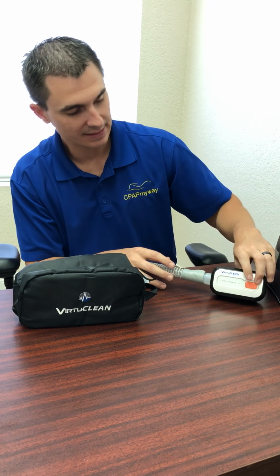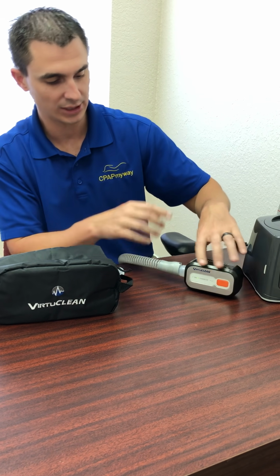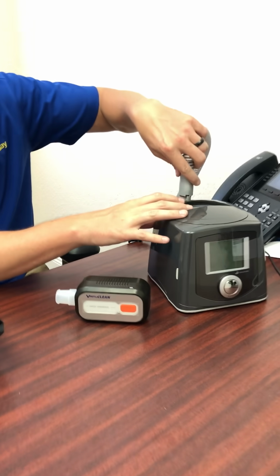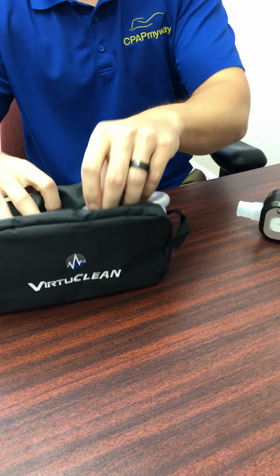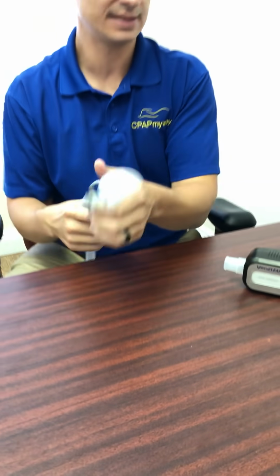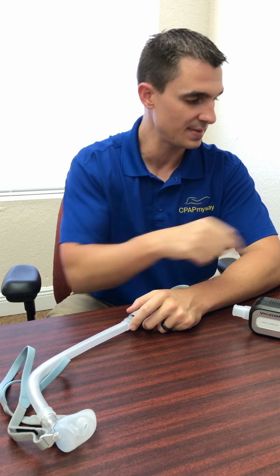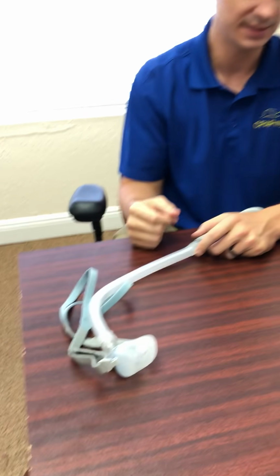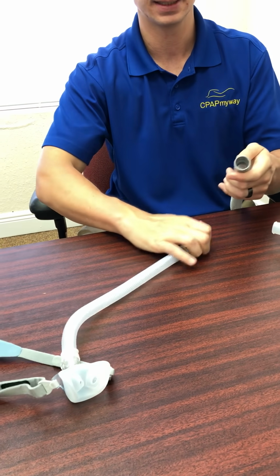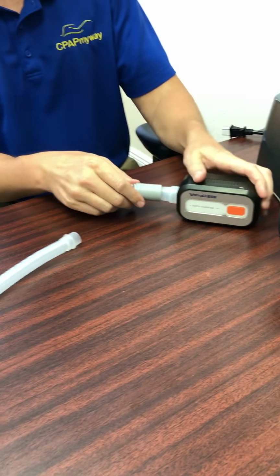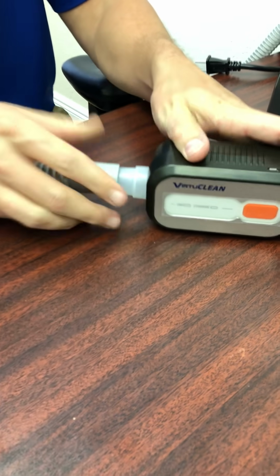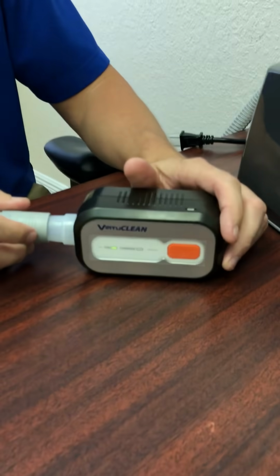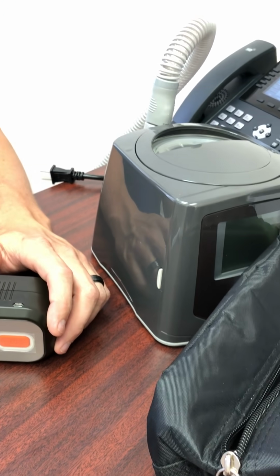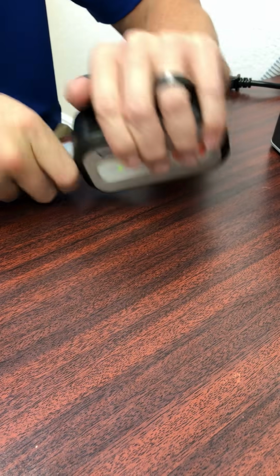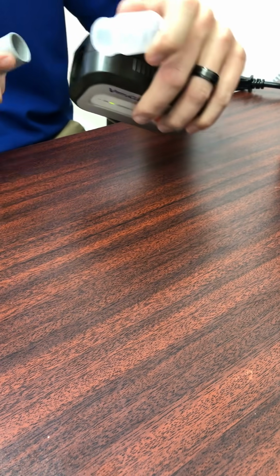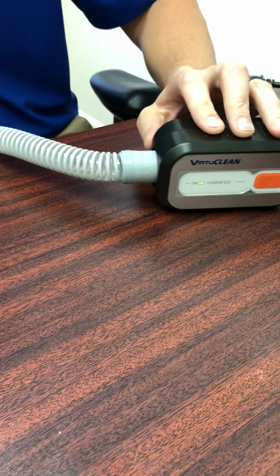The next question that we get a lot about this is, how do I sterilize the machine? Well, that's a good question. And the answer is a really short answer, and it's that you do it in reverse. So obviously to sterilize the mask, we disconnected the tube from the machine. To sterilize the machine, we do the exact opposite. We disconnect the tubing from the mask, and we connect the tube onto the device itself. Then we just turn the device on, and it runs through the system, sterilizing the humidifier and reservoir. I'm gonna take this little adapter off here so you can see it plugged on there directly. Just like that. Okay.